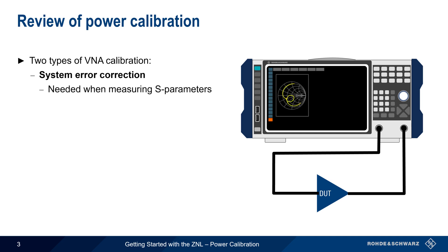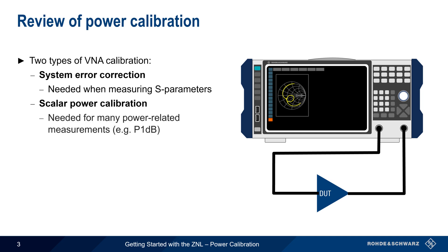Let's start with a very brief review of power calibration. There are two general categories of VNA calibration. The first, and most common, is system error correction, which is needed when making S-parameter or ratio type measurements. The second is called scalar power calibration, or simply power calibration. This type of calibration is needed when making some types of wave or power-related measurements, such as measuring gain compression or the 1 dB compression point.